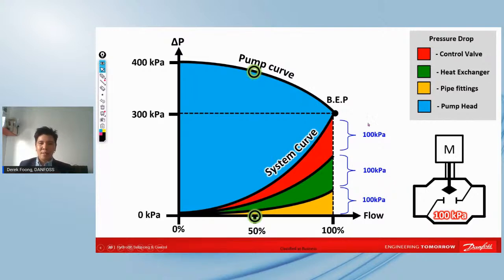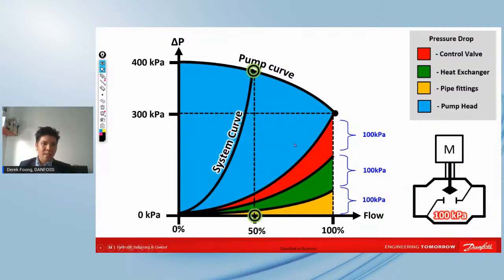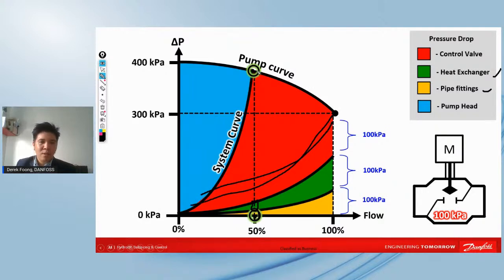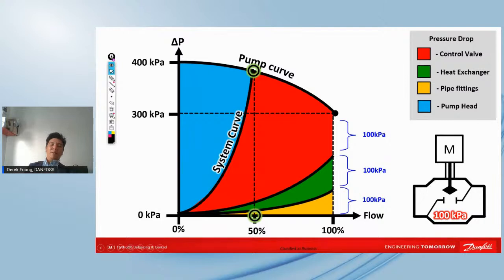And what we know is that this red color is the control valve, and the pressure would actually be transferred to the control valve. You can see that in the red area, before that the pressure drop was less, and the new pressure drop is actually bigger, right? So what is left to the rest of the equipment, the pipe fittings and the heat exchangers, is a lot lesser, exponentially. And the pressure, which was around something like this before, was at this area. Now of course there's some formula to back this up, but here on the surface, we want to keep it as a simple illustration.